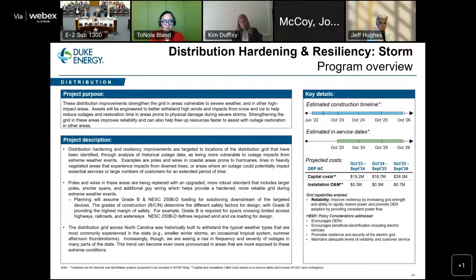Looking at our coastal areas and mountains to assess potential tropical impacts, as well as winter weather, icing and others. At the heart of it, it involves grade B construction and NESC 250B to D loading. The simple boil down of that analysis is that in areas with a propensity for higher winds and heavier ice loads, we install larger and stronger poles, shorter spans between poles, and additional guying to support those structures in the event of high winds and ice loading, where we've seen it happen repeatedly.